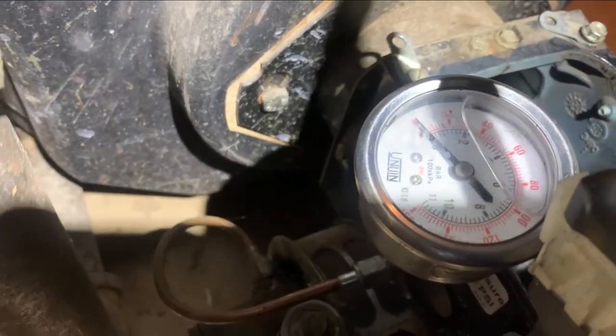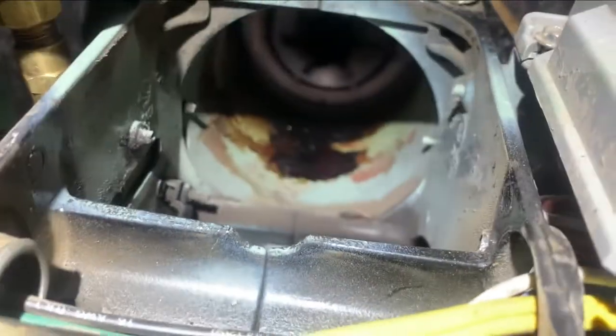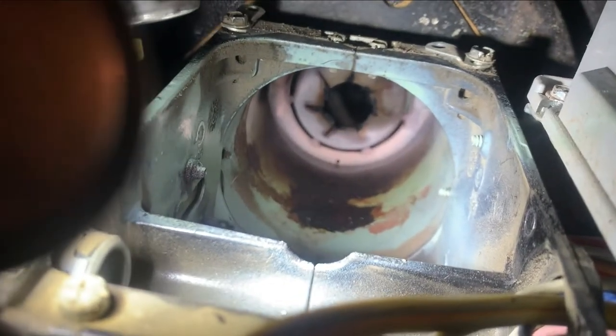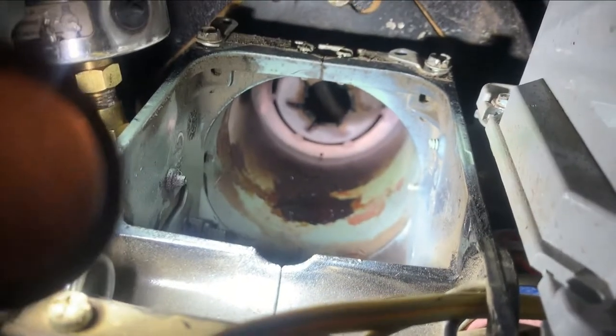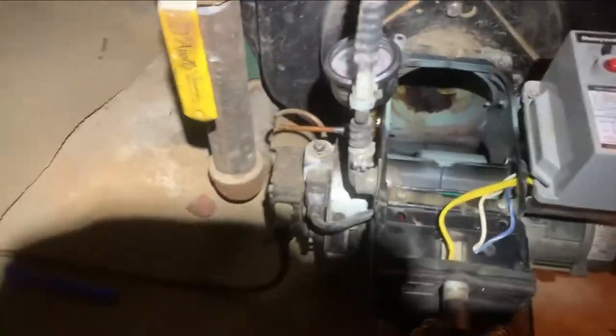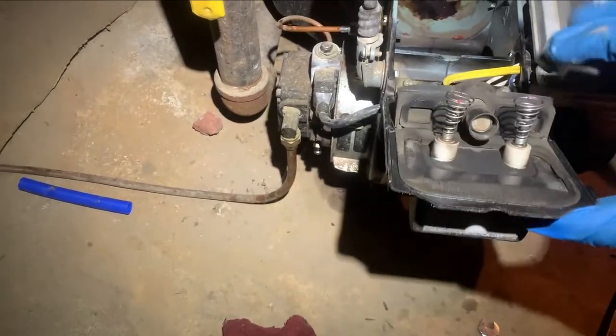I should be reading around 100 PSI coming out of the oil pump. I'm going to look inside there to see how my retention head looks, and it is a little dirty, so I'm going to take a rag in there and clean that out.